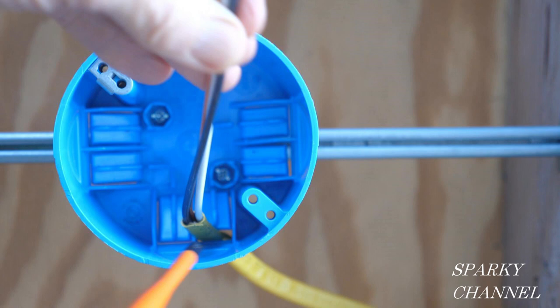For my personal opinion, I don't think that these integral clamps should have to be counted for box fill. However, as a licensed electrical contractor, I'm going to use them for box fill because I don't want to flunk any inspections. And that is just not something that I would want to get into an argument with with an inspector. So I'm going to count them as integral clamps.